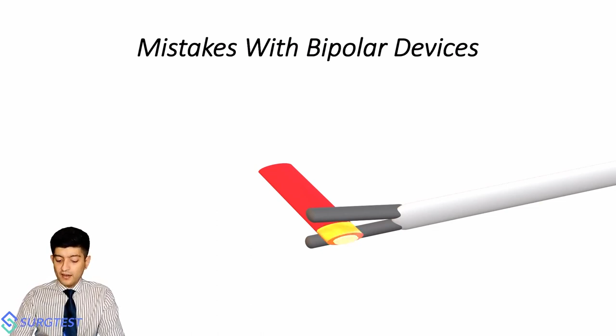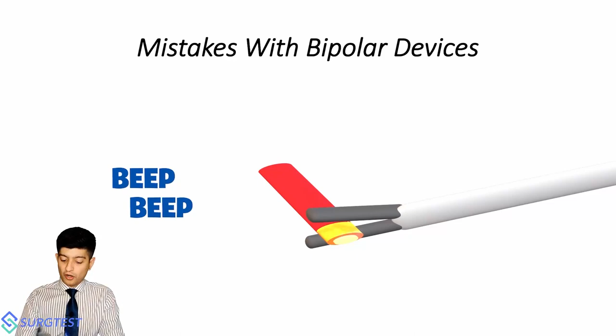The mistake that people end up making sometimes is reapplying bipolar energy over and over again. Now, say you've already had an effective seal and you reapply energy at the same spot. It's a change in resistance that the device is going to pick up. It's not going to know that you have already buzzed this area earlier. It's going to want to increase the resistance in tissues even further. As a result, the excess energy delivery will now end up charring and carbonizing these tissues, which is exactly what these devices are designed not to do. So if you keep applying bipolar energy to the same area over and over again, it is definitely possible to form an eschar, carbonize the area. When you open the jaws right now, you will end up avulsing the vessel slightly because remember, these caramelized eschars are very, very sticky.